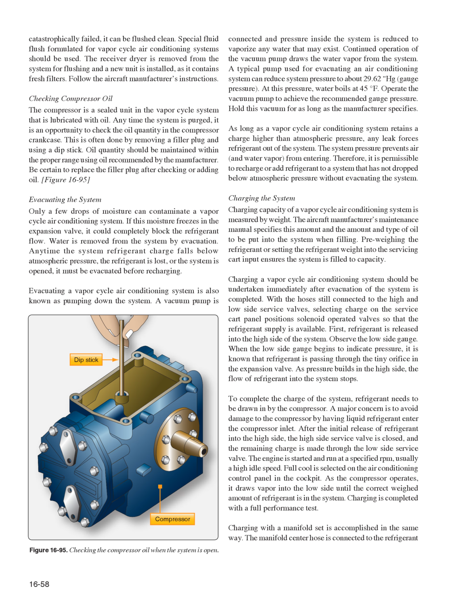First, refrigerant is released into the high side of the system. Observe the low side gauge. When the low side gauge begins to indicate pressure, it is known that refrigerant is passing through the tiny orifice in the expansion valve. As pressure builds in the high side, the flow of refrigerant into the system stops. To complete the charge of the system, refrigerant needs to be drawn in by the compressor. A major concern is to avoid damage to the compressor by having liquid refrigerant enter the compressor inlet. After the initial release of refrigerant into the high side, the service valve is closed, and the remaining charge is made through the low side service valve.